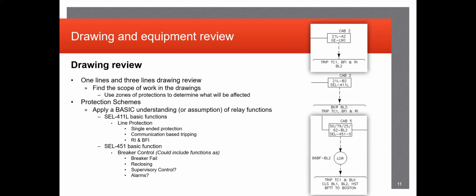It's a one-time thing. But it is extremely useful, again, for the client and the customer's sake, because if there is a quick fault and that breaker opens, that could possibly lose some customers, and it just kicks back closed, then all's good. So the breaker failure initiate is usually associated with a lockout scheme, where if there is a fault occurring in the BFI circuit, then that can actually trip out more than one piece of equipment. So if there's a heavy feed coming off a transformer side where there's multiple feeders going to different breakers and whatnot, and something catastrophic were to happen inside that circle, that breaker failure initiate could open up all pieces of equipment and save quite a few millions worth of dollars.